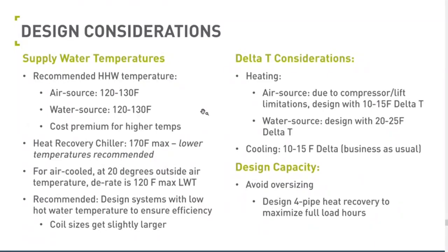Okay. So design considerations. This is going to be a little bit clunky, but mainly mechanical and plumbing focused. Historically, we've used 180 degree and 140 degree return for our heating hot water systems or domestic hot water systems. We really want those temperatures to be lower. The heat pump technology operates a lot more efficiently when it's at that lower temperature. Some heat pump technology can't even get to that 180. So it really is a factor how you're building. If you have an existing building that's sized, all the coils are sized for 180 degree temperature water. It's really hard to meet that with an efficient and non-expensive heat pump option. So supply water temperatures is big.